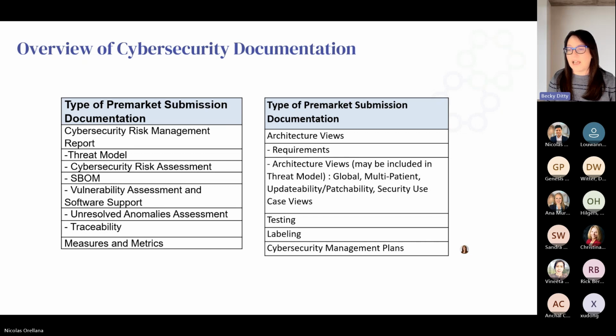The guidance document has probably 15 or more bullets of cybersecurity labeling that you need to include in your manuals. You'll want to go through and identify each of those requirements and identify to FDA where it is in your labeling. If one of those labeling requirements isn't applicable to you, don't just skip it. Still put it in your submission, but provide a justification as to why it's not applicable in your labeling. Otherwise, they're very likely to come back and say, hey, we didn't see you address this and this in your labeling. Why not? Well, at that point, then you have to try and justify why it's not applicable and hope that they agree with you.